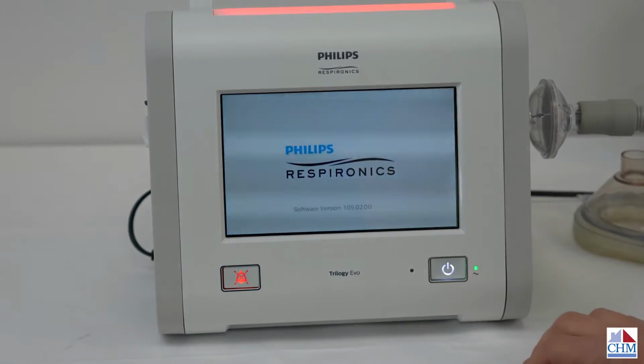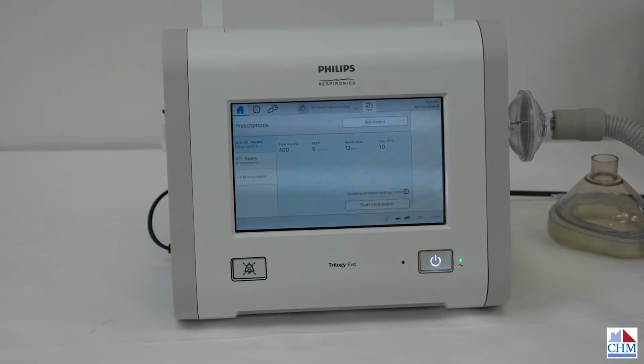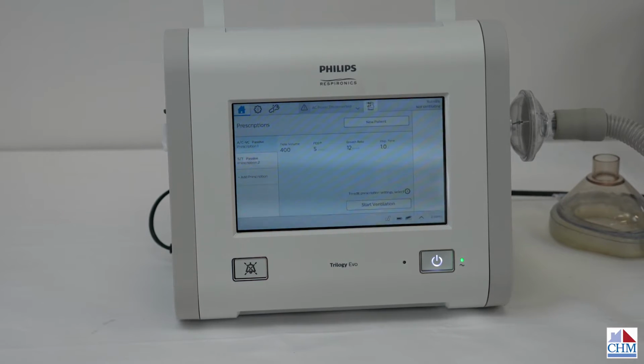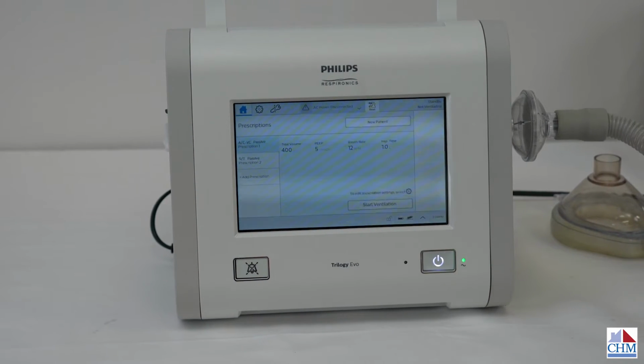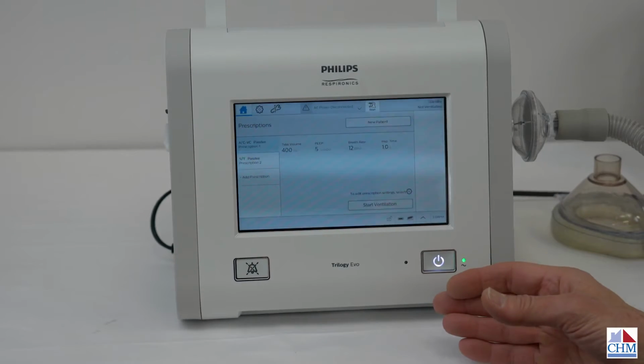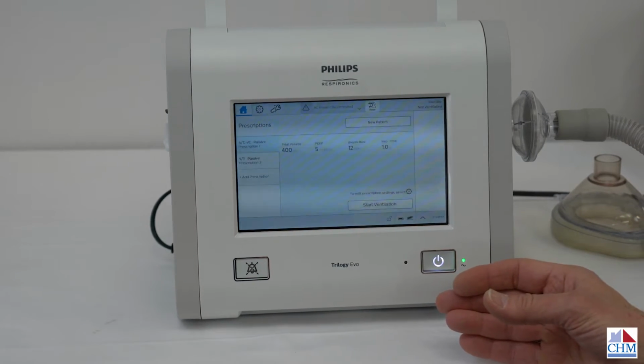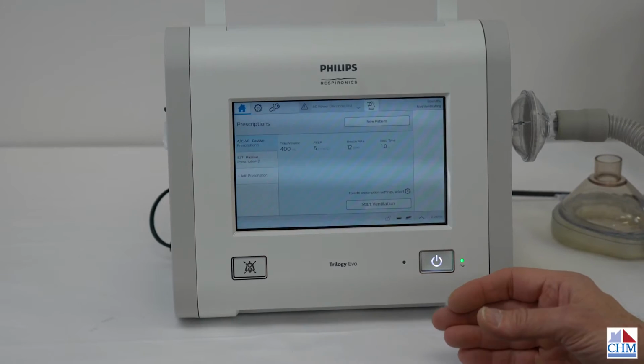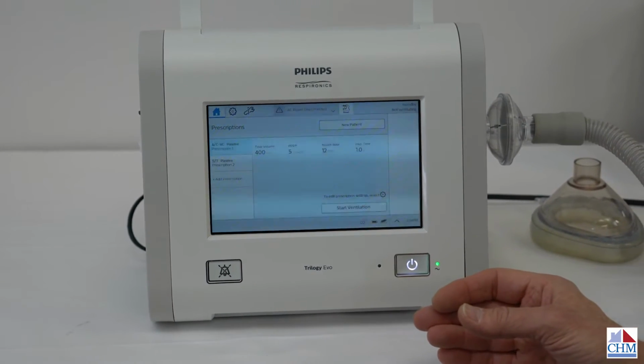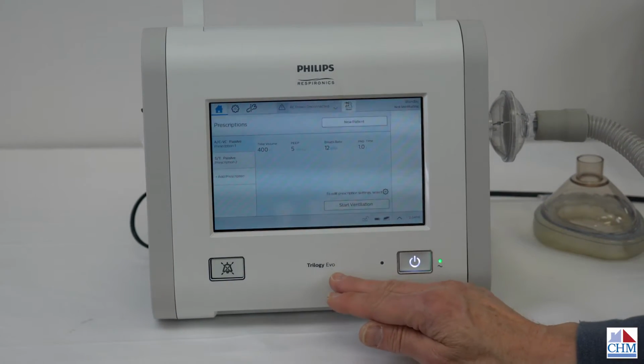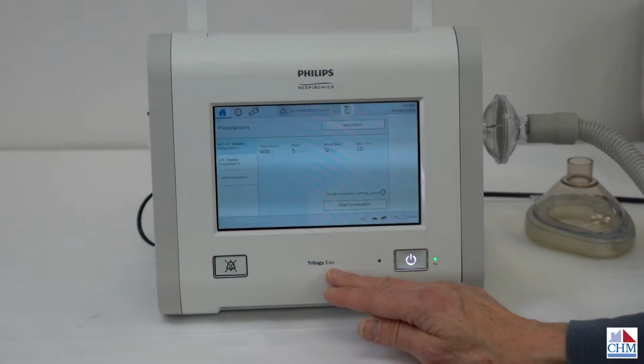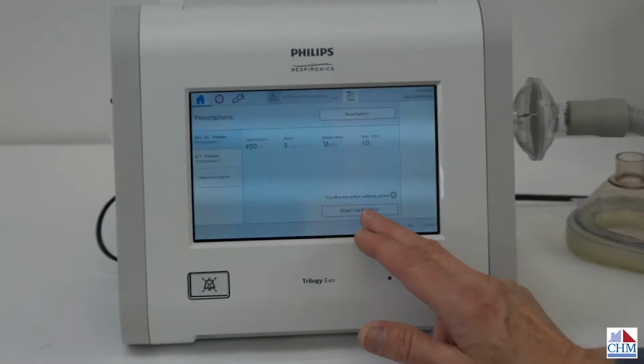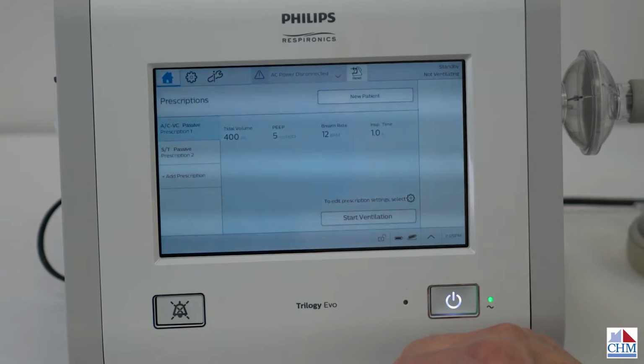Notice we get the light, we get a beep whenever you start the ventilator. And the ventilator comes up with the last settings that were on it, and notice that it comes on in standby mode. This is an important distinction between the Trilogy 100, 200 and the Evo. The Evo comes on in standby mode. So in order to start ventilation, I would hit that.